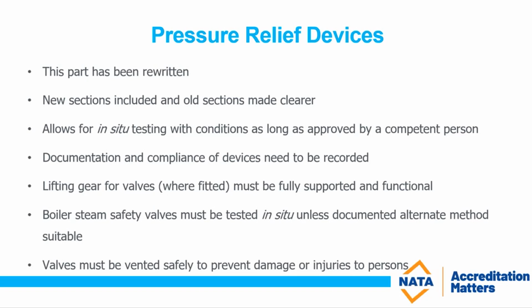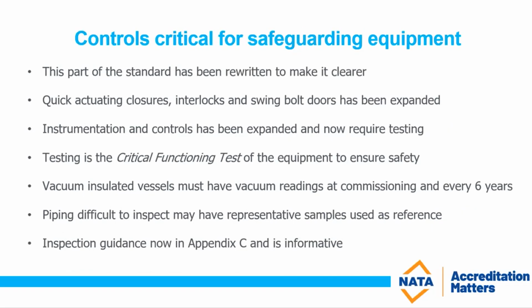Okay, we don't have any additional questions, so I'll go to the next slide. Oops, sorry. We do actually have one new question just now. Also from George Brown, a follow-up question. Does this include all the boiler management system testing? Yes, it does. The inspector has an obligation now to carry out a full inspection on all devices on a boiler for compliance to the Australian standard 2593, which is the safety management of boilers. They must go through the entire standard relevant to the boiler that they are inspecting. Okay, no more questions for now, so I will go to the next slide.